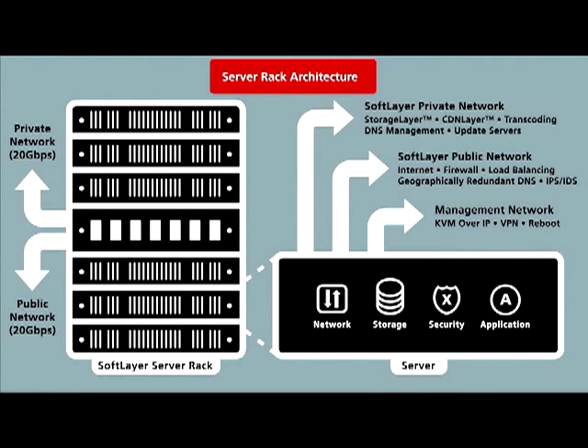Can you explain to me in a bit more detail the rack architecture in this particular center? Sure, we have a very dense rack architecture. We put 44 servers in a rack. Power is about 8 kW per rack, so we actually get about 1 server per square foot within the data center — 5,000 servers in 5,000 square feet, or in this case 10,000 servers in about 10,000 square feet.